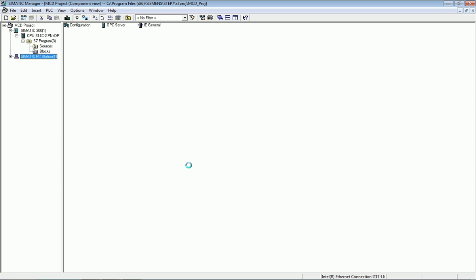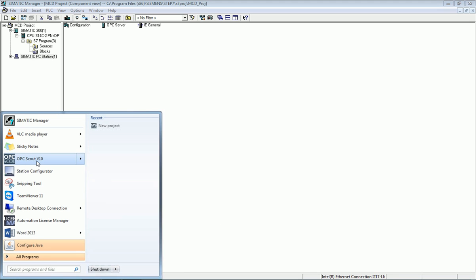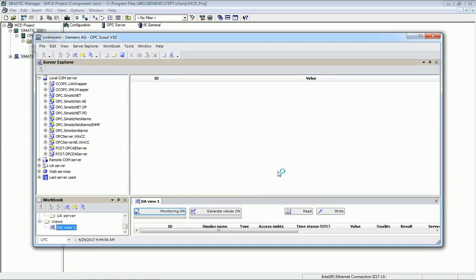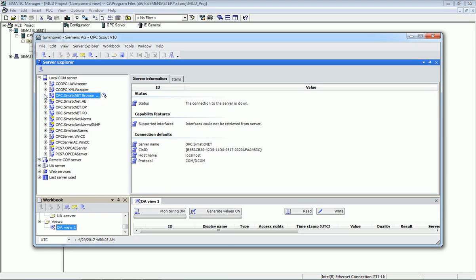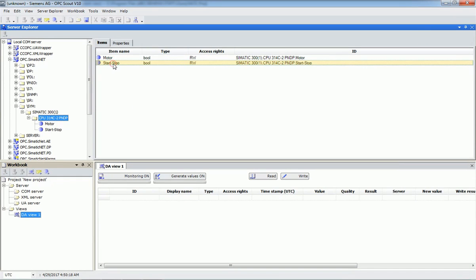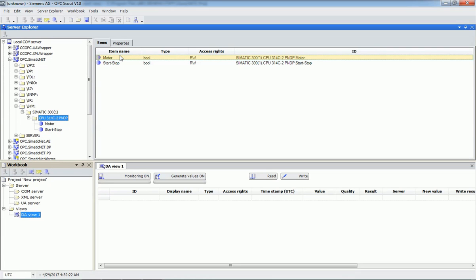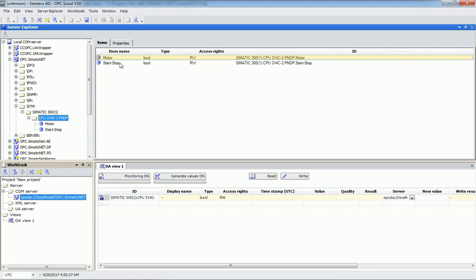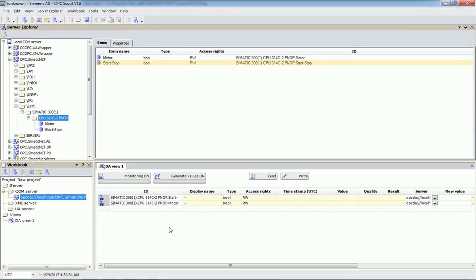We can see an option called OPC Scout — I will open that. From there we have the OPC option. We open the PLC and we are getting both variables that we defined in programming. I drag and drop both variables into the monitoring window. The ID is automatically generated. The Start/Stop variable corresponds to bit M0.0, which is responsible for motor on/off. We will control that bit from the OPC server.